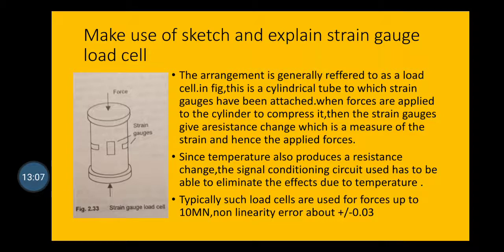Since temperature also produces a resistance change, the signal conditioning circuit used has to be able to eliminate the effects due to temperature. Typically, such load cells are used for forces up to 10 meganewton, with non-linearity error about plus or minus 0.03.